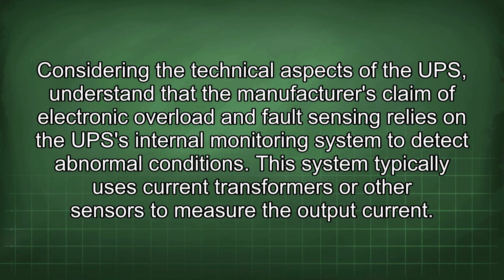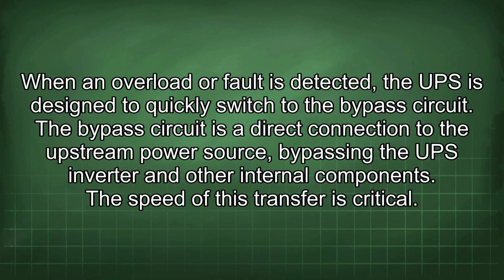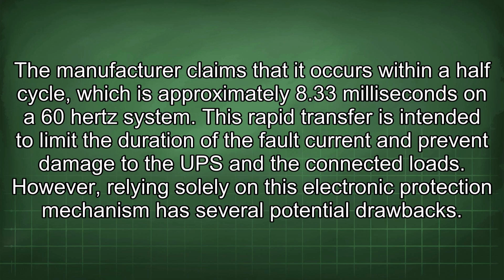Considering the technical aspects of the UPS, understand that the manufacturer's claim of electronic overload and fault sensing relies on the UPS internal monitoring system to detect abnormal conditions. This system typically uses current transformers or other sensors to measure the output current. When an overload or fault is detected, the UPS is designed to quickly switch to the bypass circuit. The bypass circuit is a direct connection to the upstream power source, bypassing the UPS inverter and other internal components. The speed of this transfer is critical. The manufacturer claims that it occurs within a half cycle, which is approximately 8.33 milliseconds on a 60 Hz system.